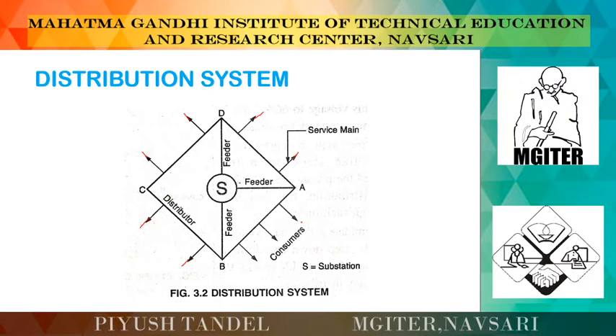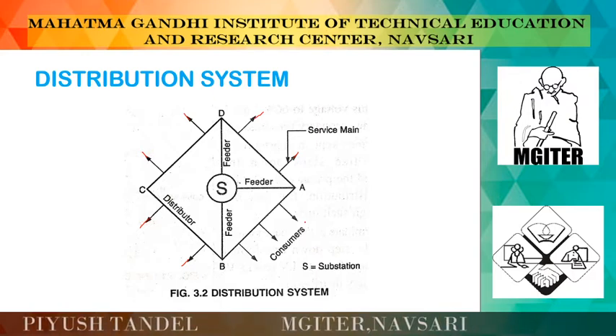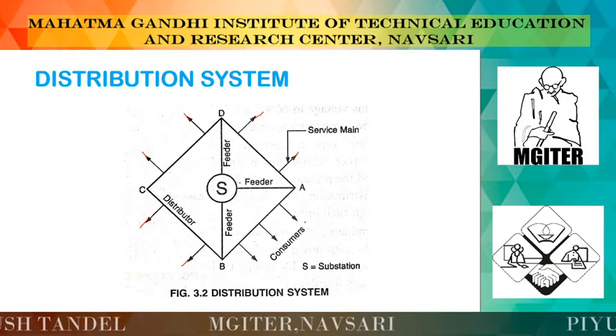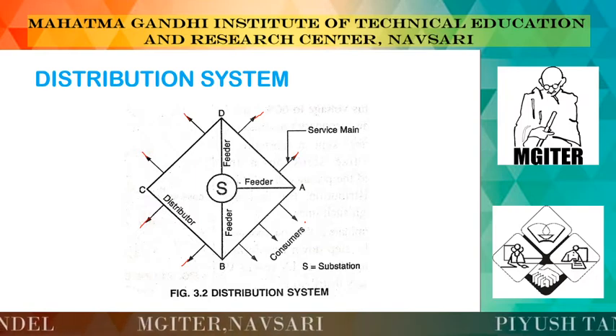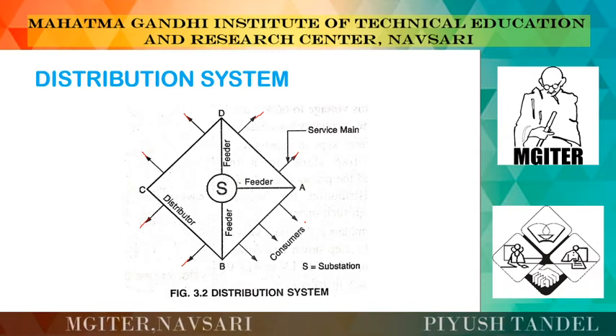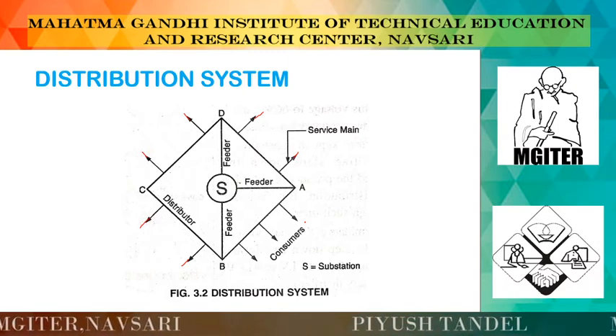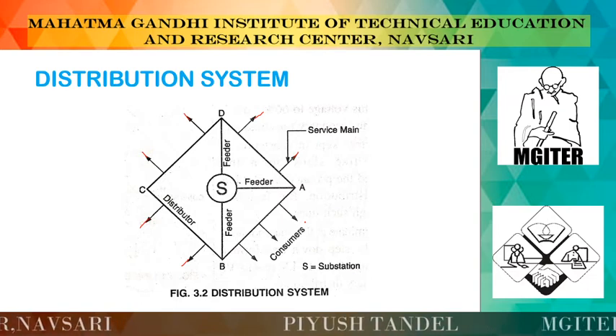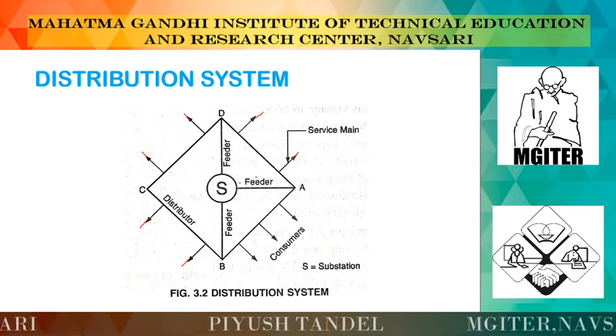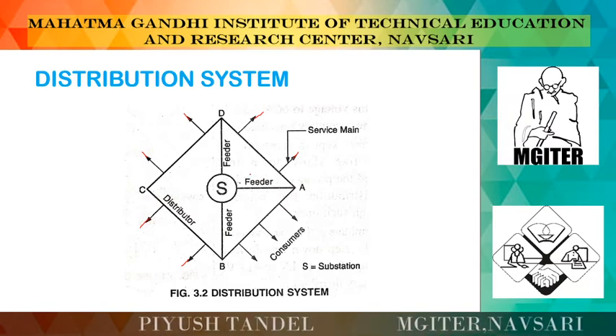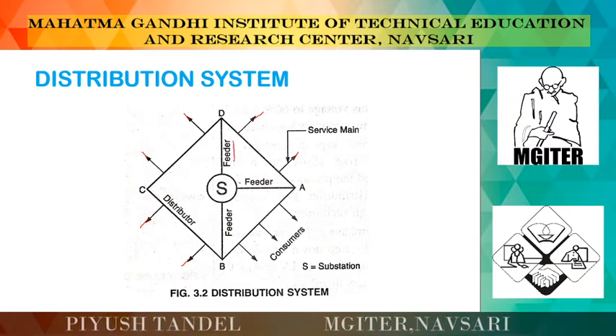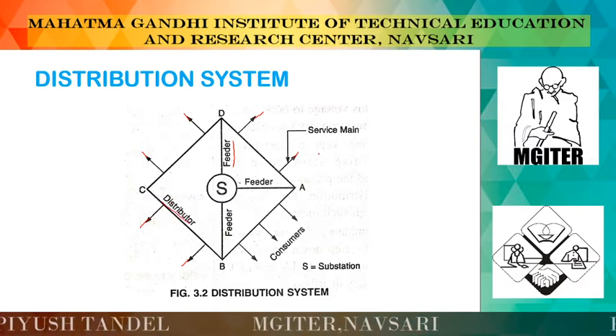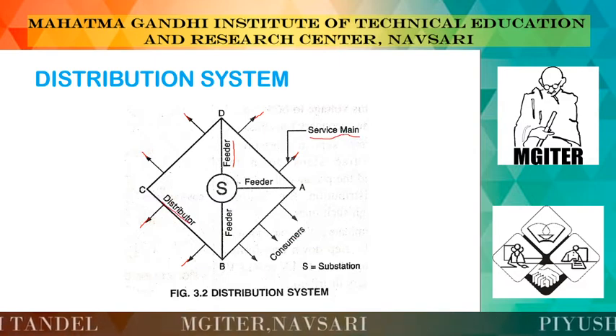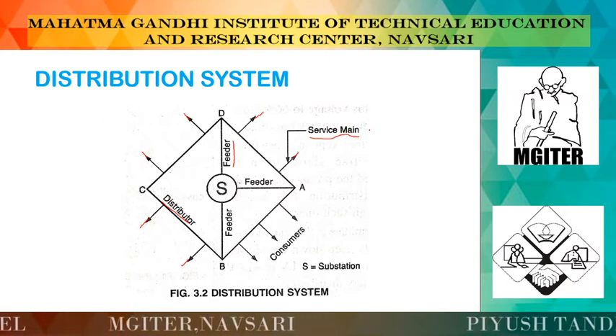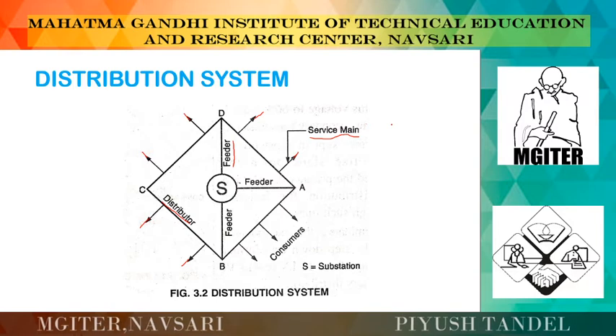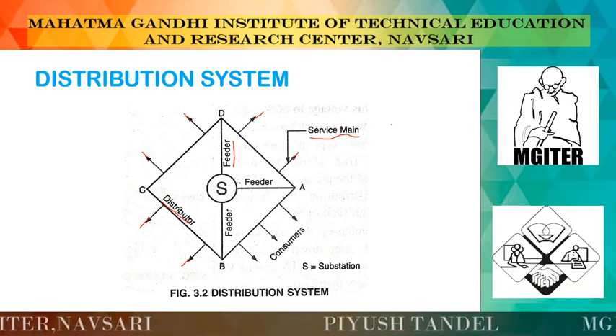And in general, the distribution system is that part of the system which conveys electrical power or energy from a major substation, which is supplied by the transmission line, to consumers as per their requirements. And a low tension distribution system is this system which comprises the feeder, distributor and service main. We need to remember these three terms: the feeder, the distributor, and the service main. Now if we talk about the feeder, it is a line or conductor which connects the major substation or localized generating station to the distributor.